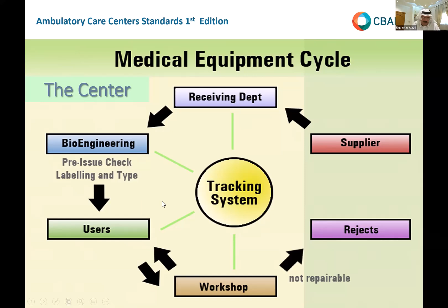And please, a tracking system. When we visit you from CBAHI, we need to see you have a record that this oximeter, this analyzer, this centrifuge, any one of them, is being maintained, the PPM. And if there was any corrective maintenance and it was sent to the workshop, it needs to be documented in the file of that medical equipment. Then if it's going to be rejected, it's gone and removed. So this is the life cycle of the medical equipment. It's very important to understand it and make sure you are monitoring and registering the whole lifetime and the movement of the medical equipment within the center.